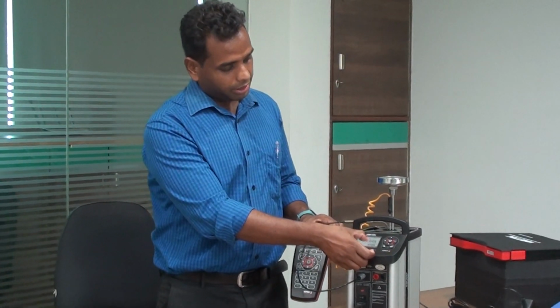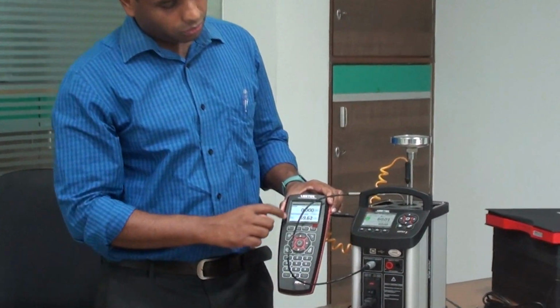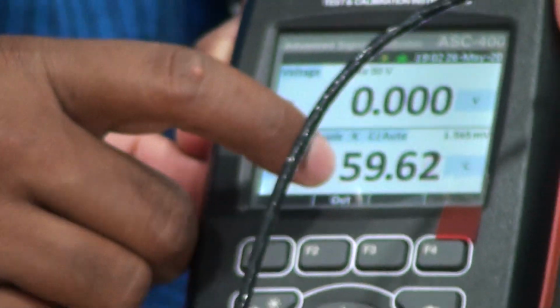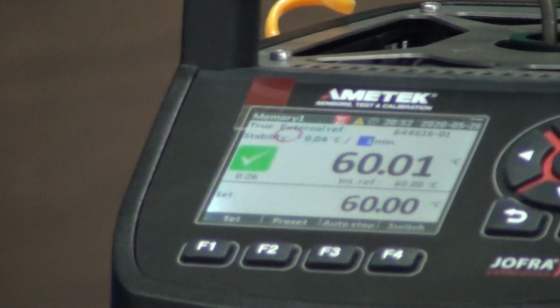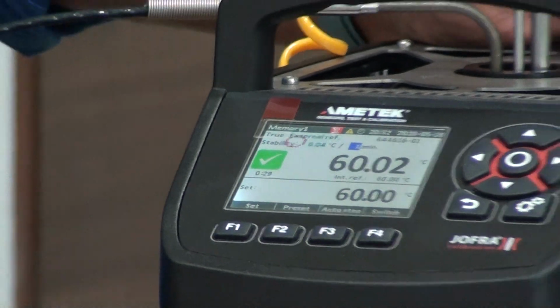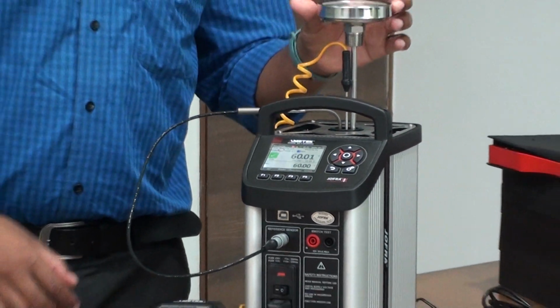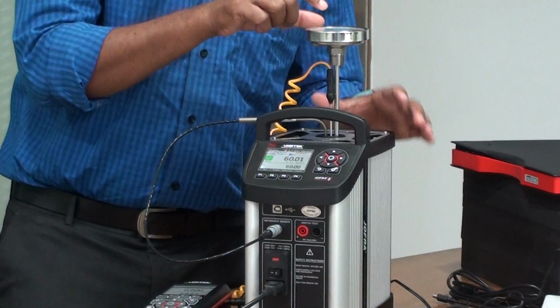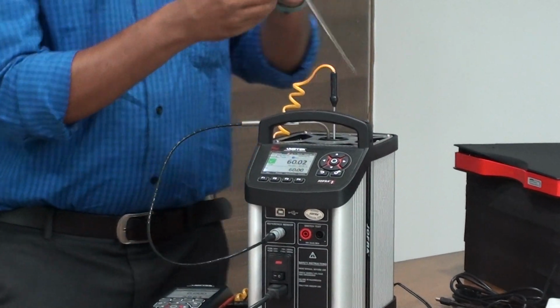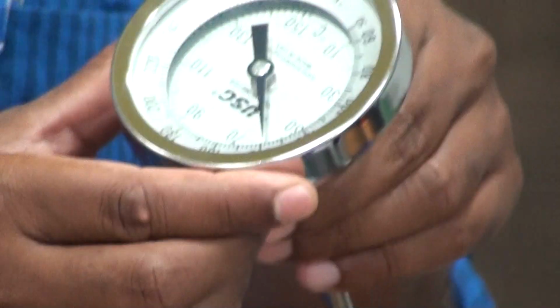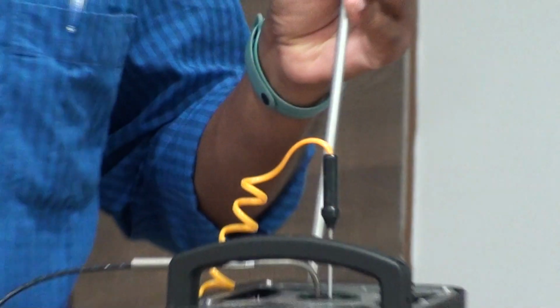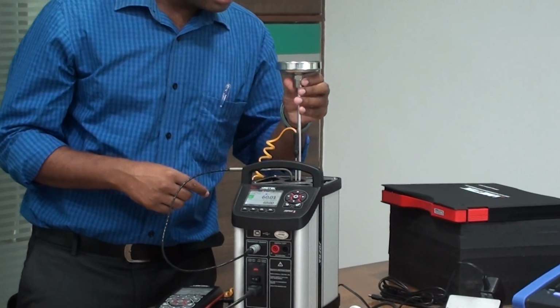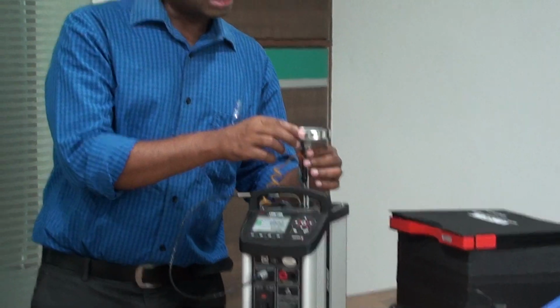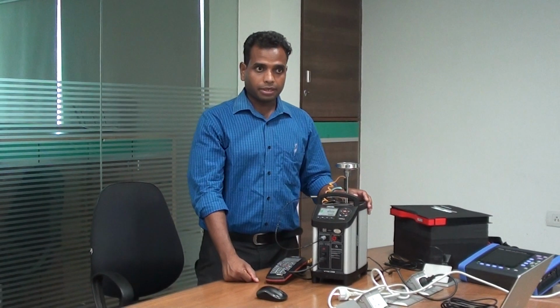So there is 61 degree, 60.01, and now it is 59.62. That means there is a deviation of 0.4 degree in the sensor with the master. For cross verification, I kept one USG analog gauge, just to check whether this sensor and that sensor are working fine or not. The analog gauge is also showing exactly 60 degree, but we cannot rely on this analog gauge. There will be some deviation due to metal configuration.